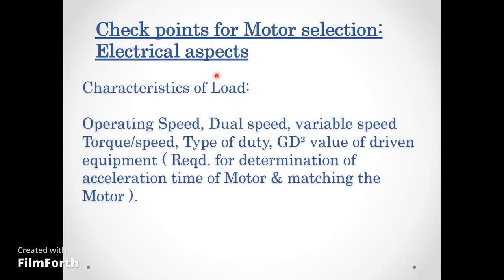From an electrical aspect, key checkpoints for motor selection include: load characteristics such as operating speed, dual speed, variable speed, torque-speed characteristics, and duty type. GD² (moment of inertia) of the driven equipment is required to determine motor acceleration time — how long the motor takes to reach full load speed — which is essential for matching the motor to the driven equipment.